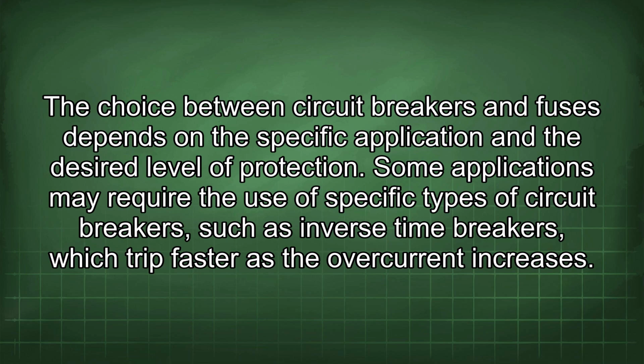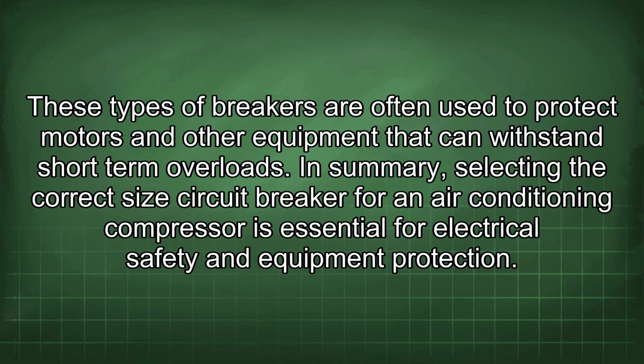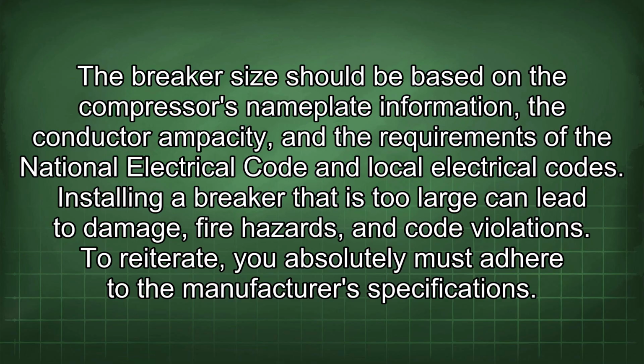Some applications may require the use of specific types of circuit breakers, such as inverse time breakers, which trip faster as the overcurrent increases. These types of breakers are often used to protect motors and other equipment that can withstand short-term overloads. In summary, selecting the correct size circuit breaker for an air conditioning compressor is essential for electrical safety and equipment protection. The breaker size should be based on the compressor's nameplate information, the conductor ampacity, and the requirements of the National Electrical Code and local electrical codes.